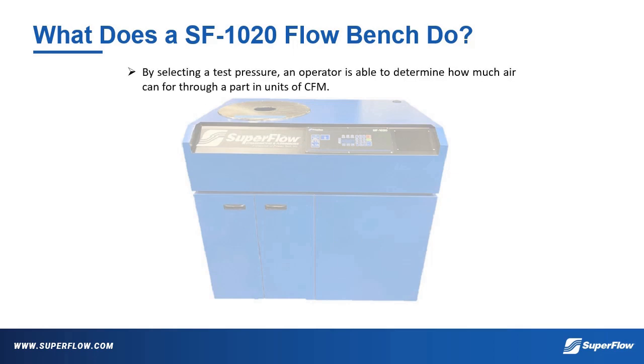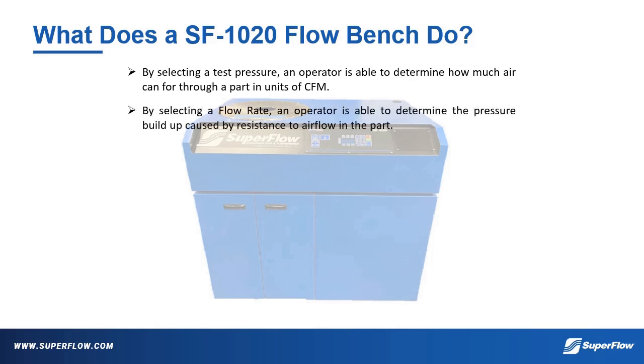Simply put, by selecting a test pressure, an operator is able to determine how much air can flow through a part in units of CFM, or cubic feet per minute. By selecting a flow rate, an operator is able to determine the pressure buildup caused by resistance to airflow in the part. Testing beyond the actual capacity of the flow bench is possible.